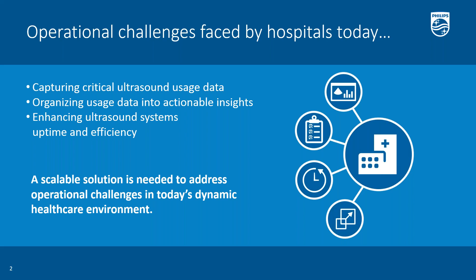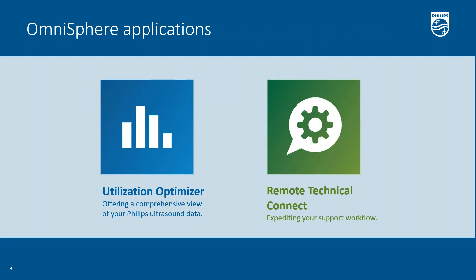Omnisphere is a software-only platform that connects you to your Philips EPIQ or Affiniti ultrasound systems and their data. Omnisphere consists of two applications to aid in optimizing your ultrasound business. The first is Utilization Optimizer, which offers a comprehensive view of the Philips ultrasound utilization data. The second is Remote Technical Connect, which enables internal biomed or clinical engineering departments to expedite technical support to eligible Philips ultrasound systems.